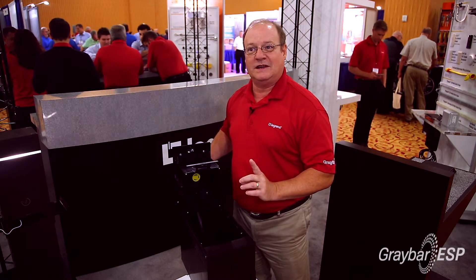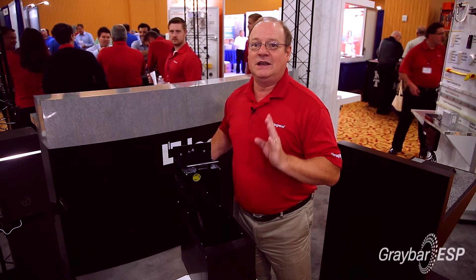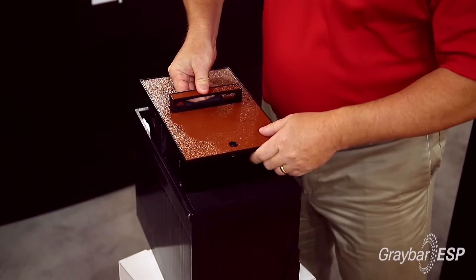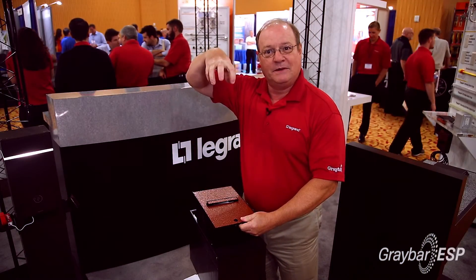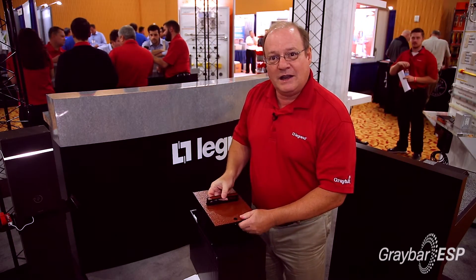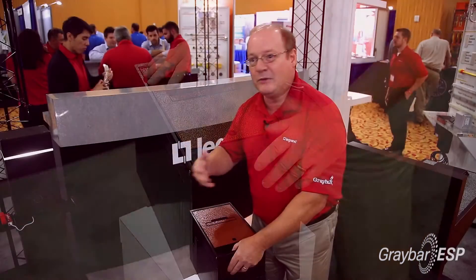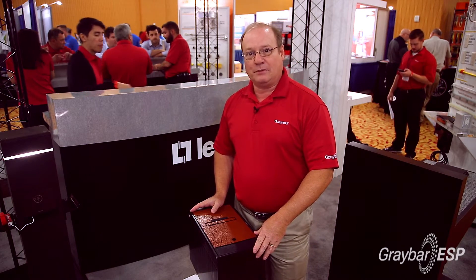What's unique about this is it's the only box right now that you can use during inclement weather — where it's raining and pouring — because as you close this box, it creates an airtight seal and, like a cup, keeps all the electrical connections out of the water. It creates an air pocket that holds that, and the cable egresses right out of the cabling here so you can connect your banquet cables or whatever installations you have set up as temporary power.